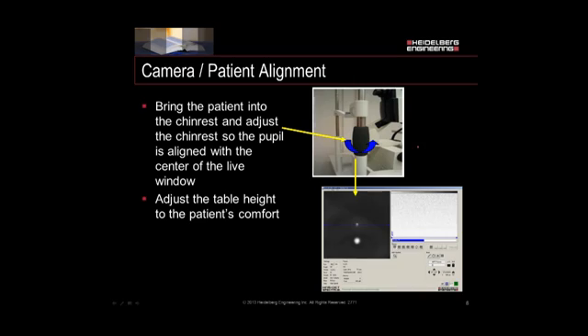Once you activate the eye tracker, make sure you let the ART frames build up to 100. Sometimes it may not reach 100 if patients have difficulty fixating, but let it build up as much as possible — the more ART frames, the better the overall image quality. Remember: make sure your fundus image is evenly illuminated, you have good focus — which means brightness — and you have nice even density along the retinal pigment epithelium. To activate the eye tracker, push the black gain button on the touch panel or hold down the joystick button for one second. To take the picture on the touch panel, press acquire, or on the joystick model, press the button quickly.